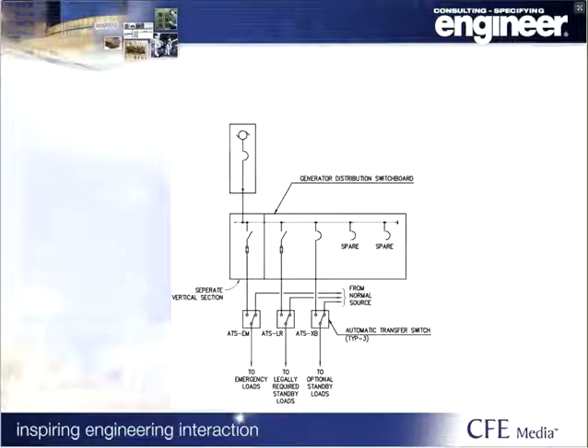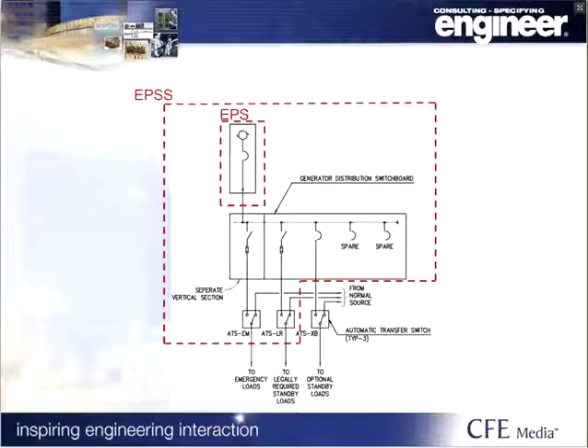Here we have a simple generator system diagram. The generator and the disconnecting device located on the generator make up the EPS. The EPSS includes all parts of the EPS plus the generator distribution board, the emergency and legally required transfer switches, and, although not indicated here, all controls and wiring between the transfer switches and the generator control panel.